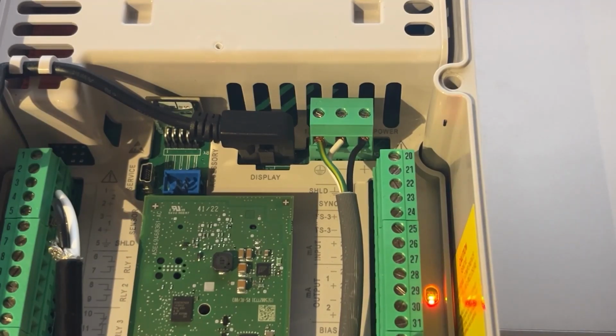As the device is coming online, we can see that our alarms are starting to clear, and now we are in a good status. We can see that solid green light, which means that we don't have any issues right now. And when the device is powered, you'll always have that green LED. If you have a steady red light there, that means that you have an active maintenance alarm. A fast flashing light means that you've got an active function check. A slower flashing red light means that there's an active process alarm or warning. And a yellow light means that the device is responding to a field bus request.